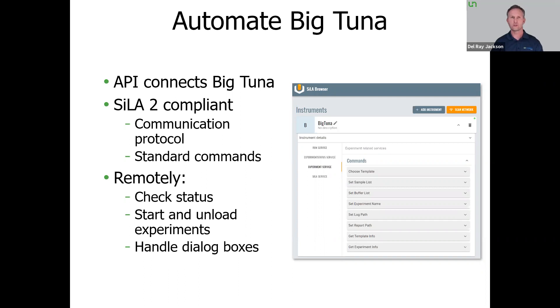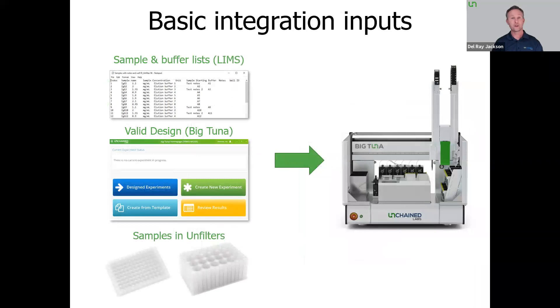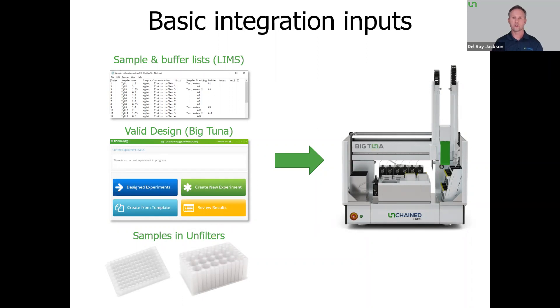The API lets you do things like remotely checking status, starting and unloading experiments, and handling dialogue boxes. Integrating BigTuna into your overall lab process, workflows, or automations is even easier. The sample and buffer list can be automatically taken from your LIMS and imported into BigTuna. The BigTuna software makes it so easy to set up your buffer exchange and concentration protocols with those preset values and also validates them for you.